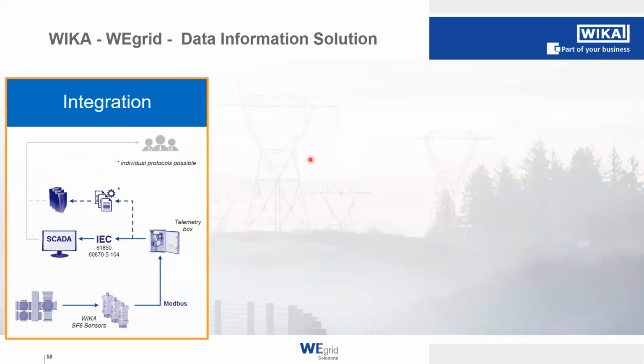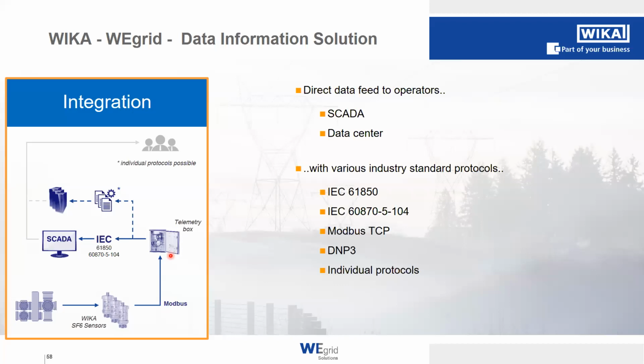The next solution, the second variant that we have, is a little bit different. As you can see on the bottom, we are also equipping the GIS with our sensors, and the sensors are connected via a Modbus line to a telemetry box. And in this telemetry box, the data is being consolidated as before, but the difference here is that it is converted into a different industry protocol in order to fit the customer's SCADA system or the customer's data center. That means in this gateway, we are able to provide different protocols such as the most recent IEC 61850, but also older protocols such as IEC 60870, or general protocols such as Modbus TCP or DNP3.